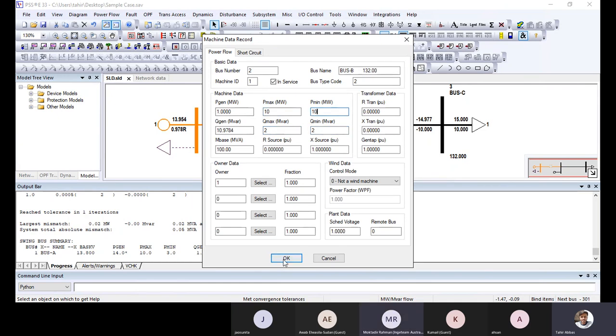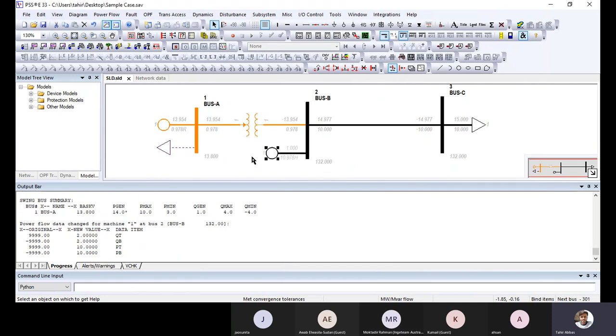I'm changing the parameter to describe the answer to your question. Otherwise, we cannot change parameters like this. Every generator has its own specification and its own generator capability curve, and we will set those parameters. Now you see that I have a demand of 10 megawatt. Now I solve.